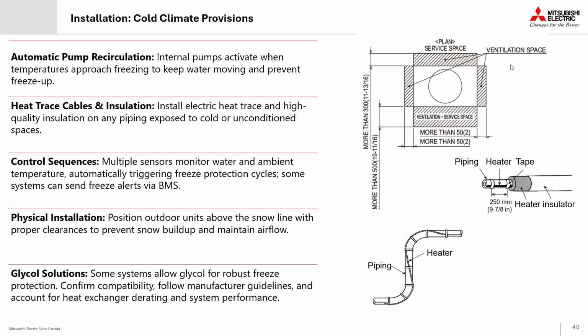We need to be aware that there will be periodic defrost cycles required in those colder months, usually between, let's say, 2 degrees Celsius and -5, where we're still able to have very cold but humid air in our outdoor space. We need to offer provisions to allow that system to defrost and for that water to drain away from our unit.